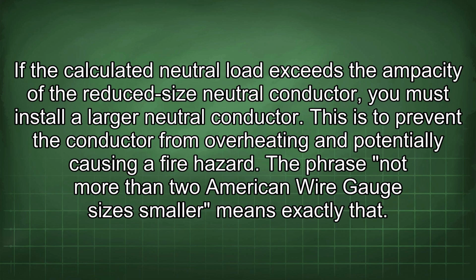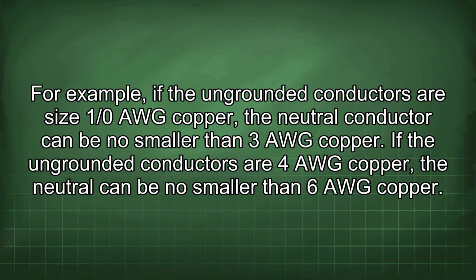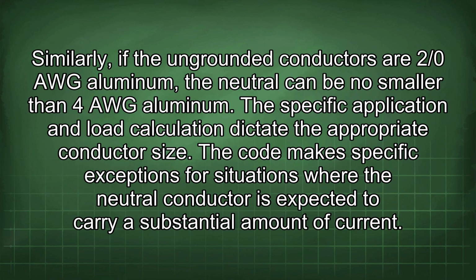The phrase "not more than 2 American Wire Gauge sizes smaller" means exactly that. For example, if the ungrounded conductors are size 1/0 AWG copper, the neutral conductor can be no smaller than 3 AWG copper. If the ungrounded conductors are 4 AWG copper, the neutral can be no smaller than 6 AWG copper. Similarly, if the ungrounded conductors are 2/0 AWG aluminum, the neutral can be no smaller than 4 AWG aluminum. The specific application and load calculation dictate the appropriate conductor size.